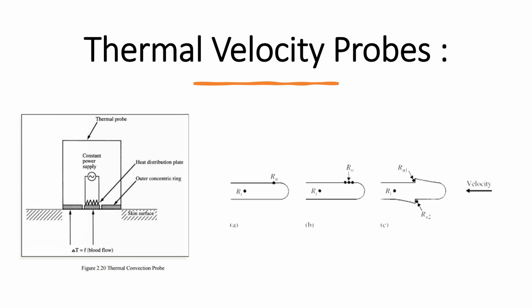Also, as shown in figure C, the probe uses two velocity sensors arranged so that one is exposed and the other is shielded from the fluid velocity. To correctly measure velocity profiles, probes can be placed at the end of a hypodermic needle and inserted perpendicular to the vessel. As shown in figure 2.20, inside the thermal convection probe there are two concentric rings and a central disk. The concentric rings are isolated thermally and electrically from each other. The central disk is heated 1 or 2 degrees Celsius over the temperature of the tissue by using a constant power supply, and a temperature difference of 2 or 3 degrees Celsius is established between the disk and the rings.